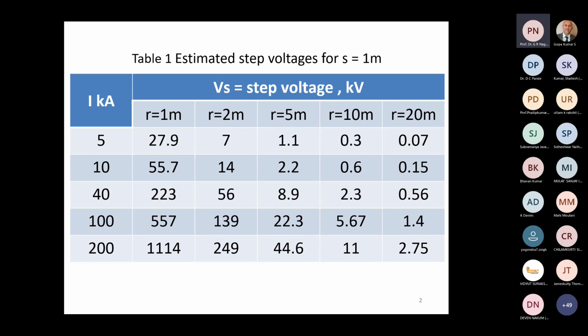we go near. For example, if we take the 40 kiloamperes current, which is the 50% probable value of the lightning stroke current, the step voltage at 1 meter distance is 223 kilovolts. If we go to a distance of 2 meters, just twice the distance, it goes down as the square of the distance. It comes down to 56 kilovolts, a substantial reduction. If we stay at a distance of 5 meters, it comes down to 8.9 kilovolts. And if we are, let us say, 20 meters away, it comes down to 0.56 kilovolts.